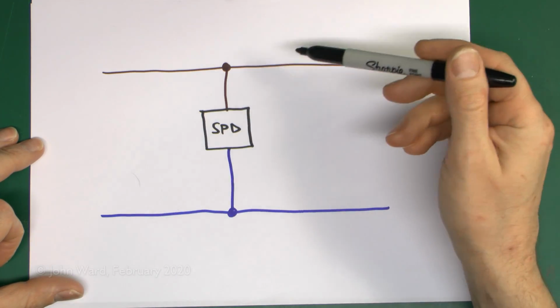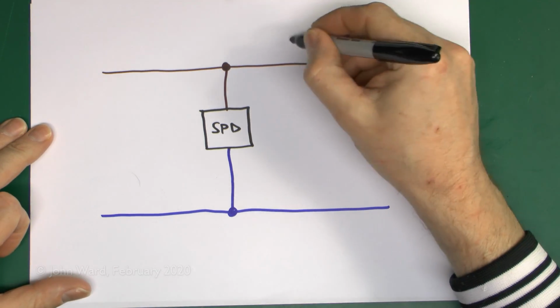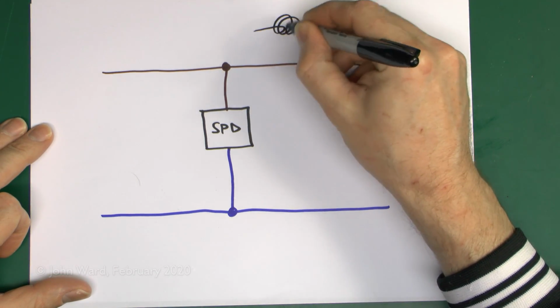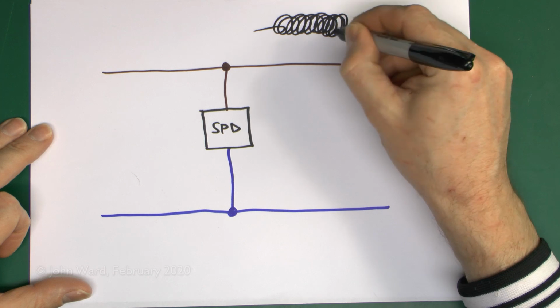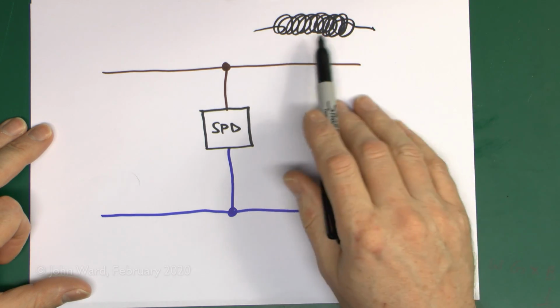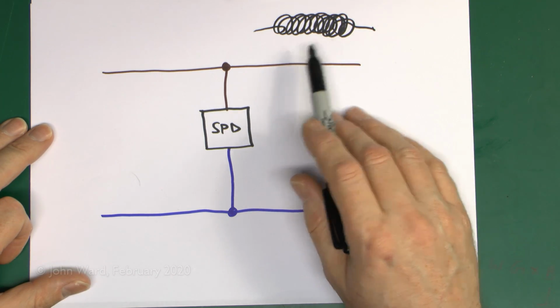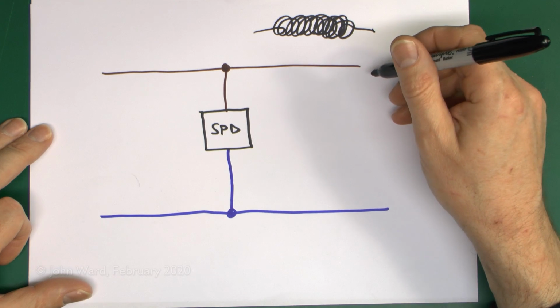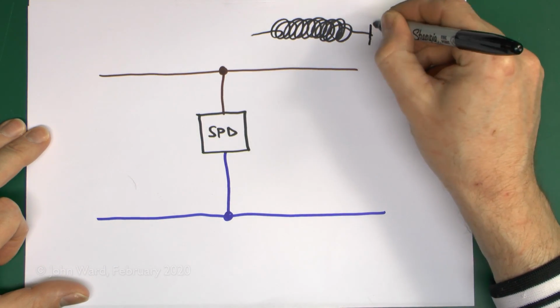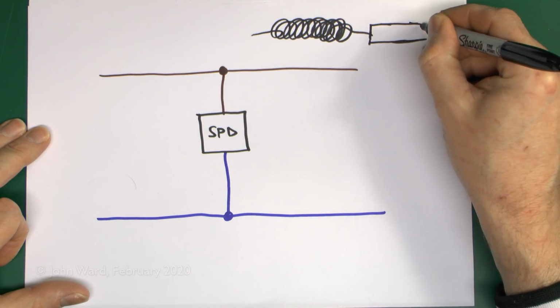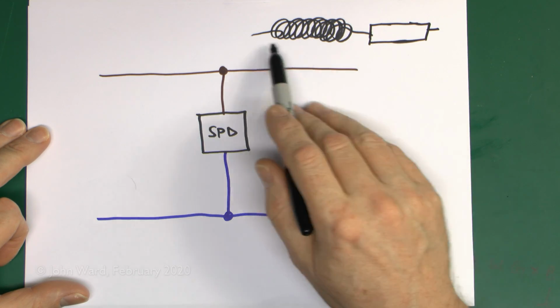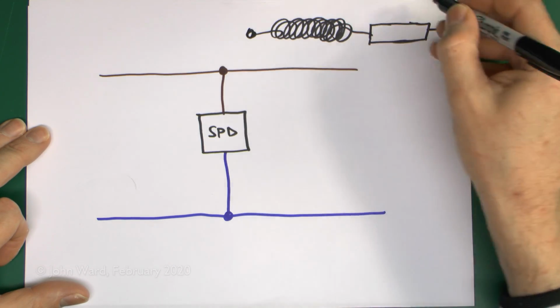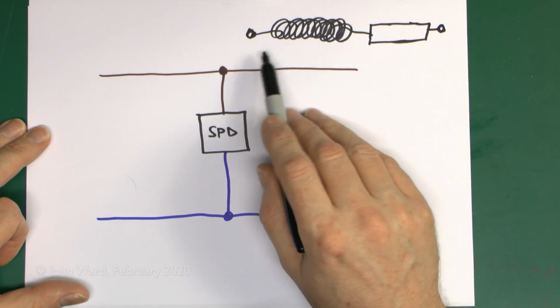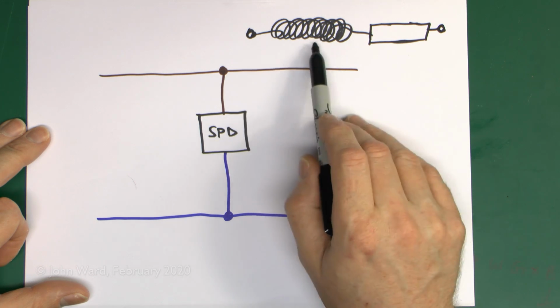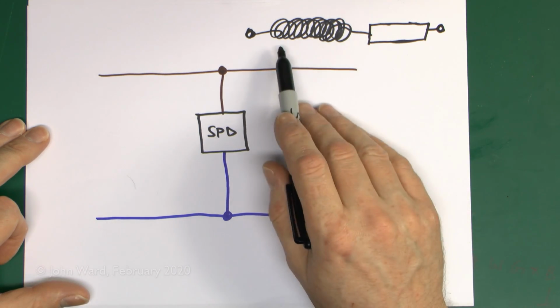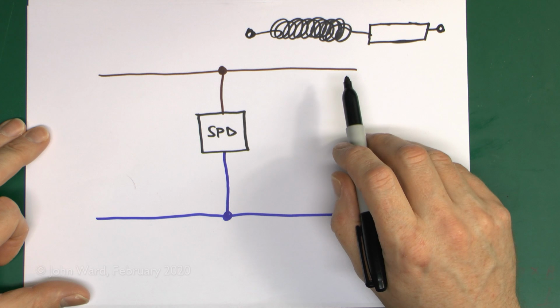Now, inductors, you might think of typically as, say, a coil of wire. So you might have a wire coming in and a big old coil of wire like that. A property of an inductor is that if you put it in series with, say, an old type of fluorescent tube and connected 230 volts to the ends of that, then the inductor, or the choke, also called a ballast, would limit the current that can flow through the fluorescent tube.